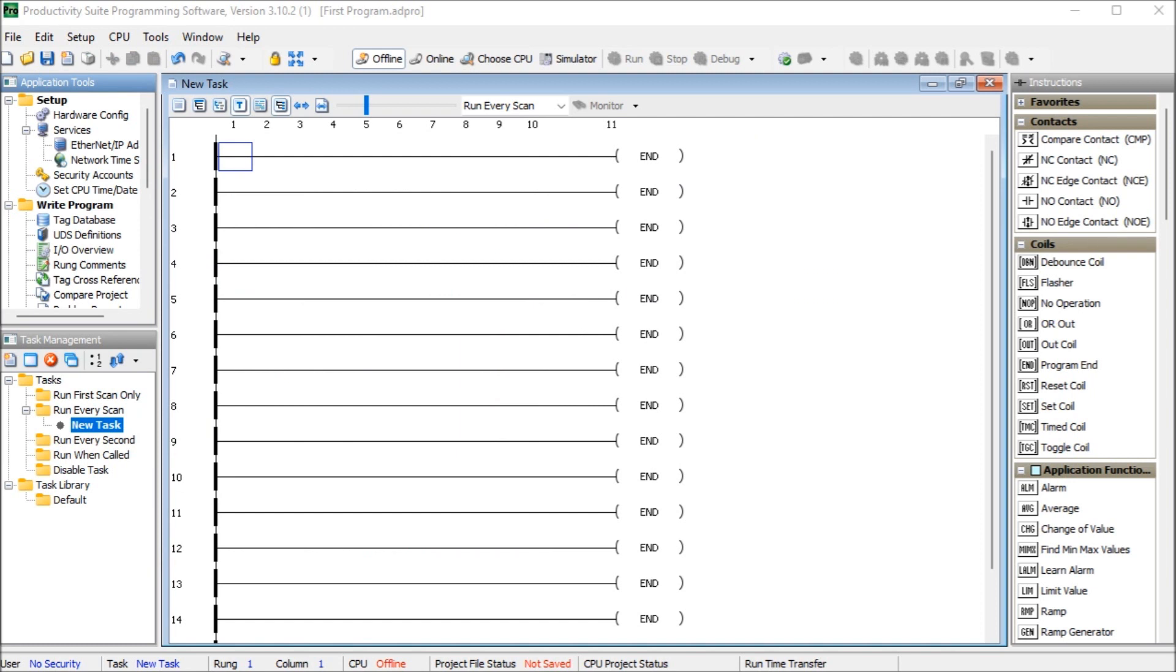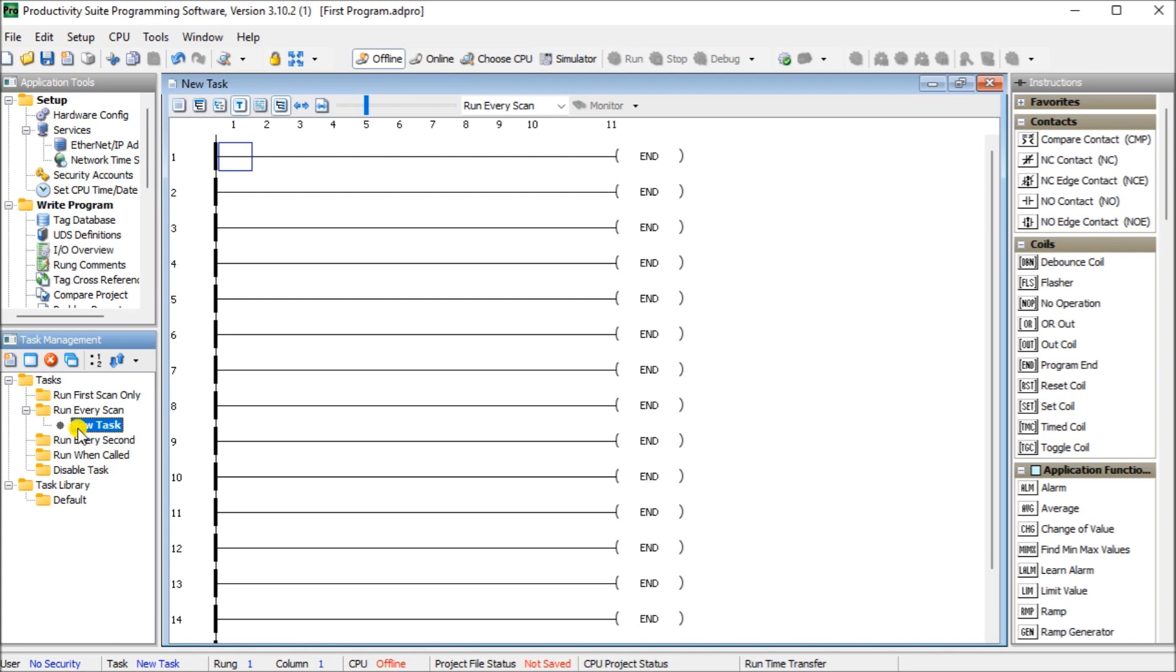Next, what we'll do is we'll look at our productivity task management. And that's this window right down here. And you can see this new task here is the same thing as this new task here. So how the productivity program is developed, basically, is a series of tasks that we have and sections that we can actually then program. Each of these sections actually have ladder logic code in them. And you can see under the task, we actually have five different areas. We have run first scan only. That means that the code that I put in here will only run when it first powers up the CPU with power. The next one here is the default one, which is our new task. It runs every scan. So typical scan that we will do for a PLC.